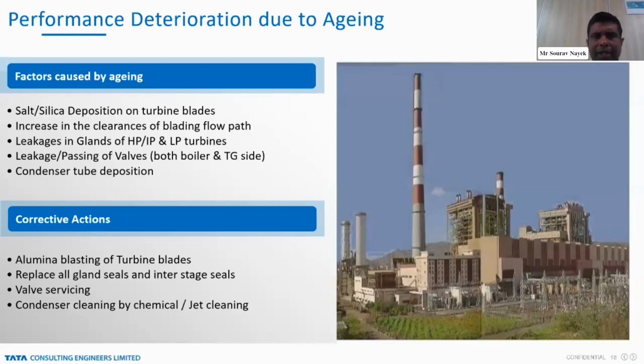On performance deterioration, as earlier speakers also mentioned, the performance of every equipment is very important to maintain the desired heat rate level. If there is any fouling or scaling in the equipment, this will create additional resistance and it will not give the desired performance. Like in the turbine, if there is salt or silica deposition on the turbine blades, this will affect the heat rate. Clearances in the flow path, gland leakages in the HP, IP or LP turbines, leakages in the valves, and condenser tube scaling all impact the performance of the plant.